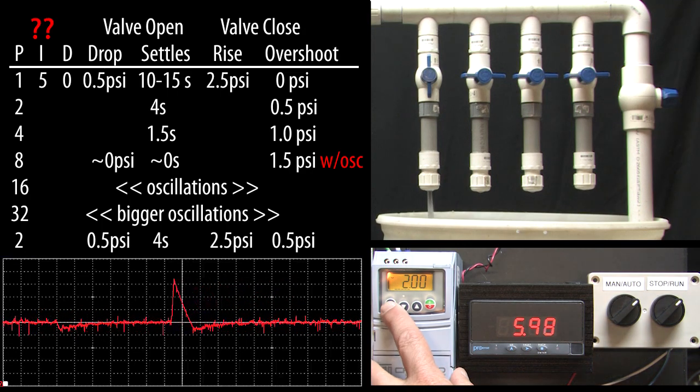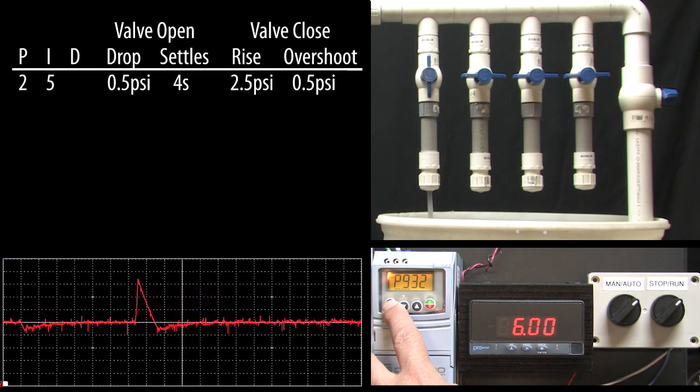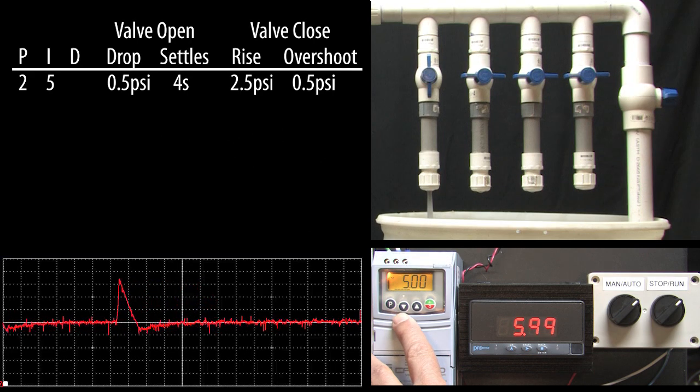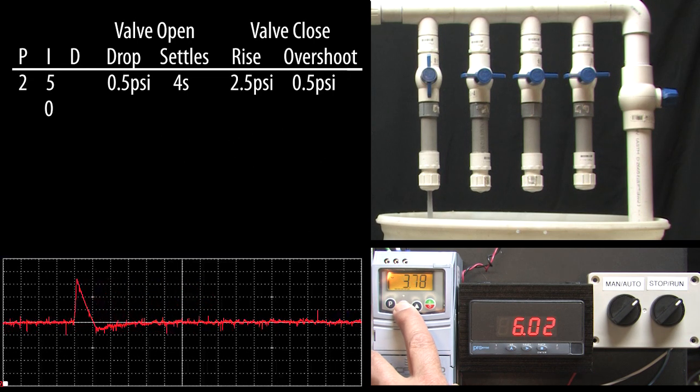How does the I term affect things? Let's go to parameter 932 and find out. The default I is 5. Let's turn it off by entering a zero. Uh oh, what happened? Our pressure dropped by over 3 psi.